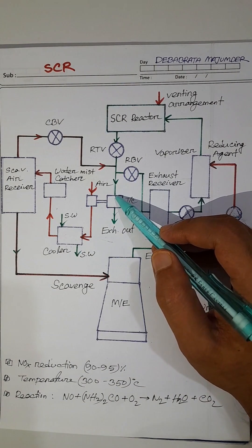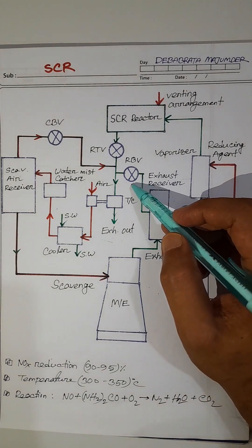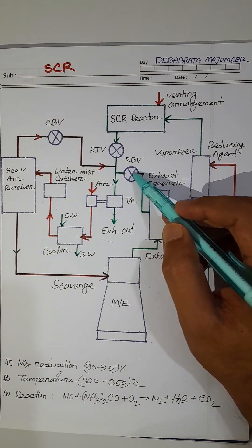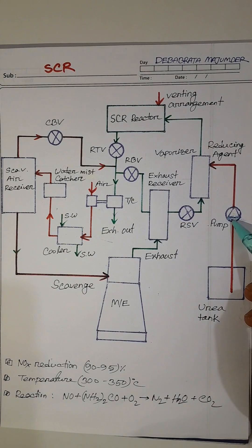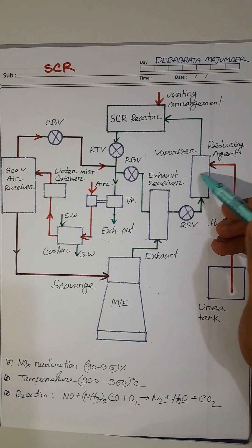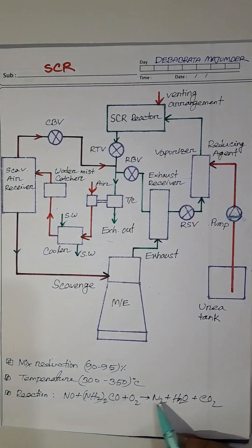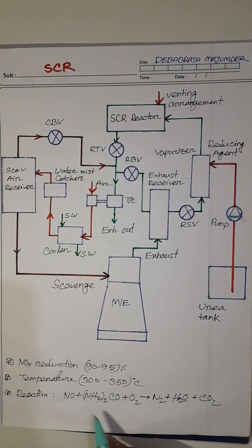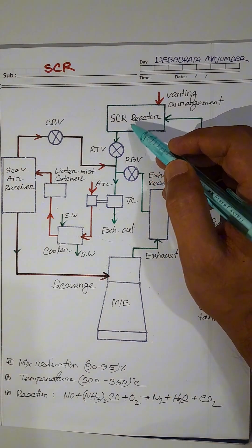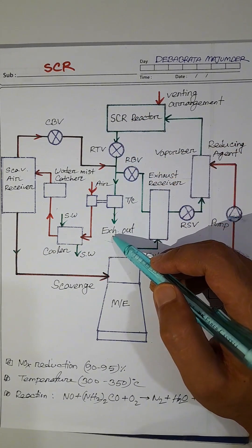Whenever the exhaust temperature reaches the desired 300 to 350 degrees centigrade, the SCR control unit gives a signal to the valve, the valve is closed, and the control unit starts the pump. Through this pump, urea is injected and mixed with the exhaust gas, passing through the reactor. Here chemical reaction occurs which converts urea and NOx into nitrogen gas — meaning NOx is converted into nitrogen gas and exhaust gas goes out.